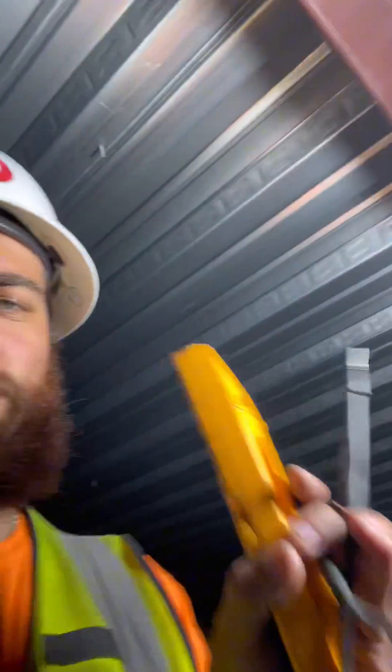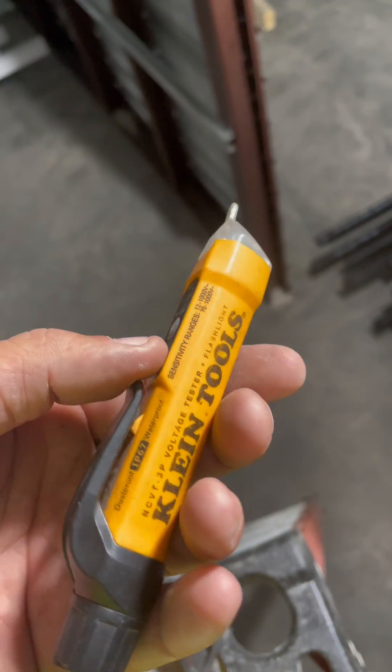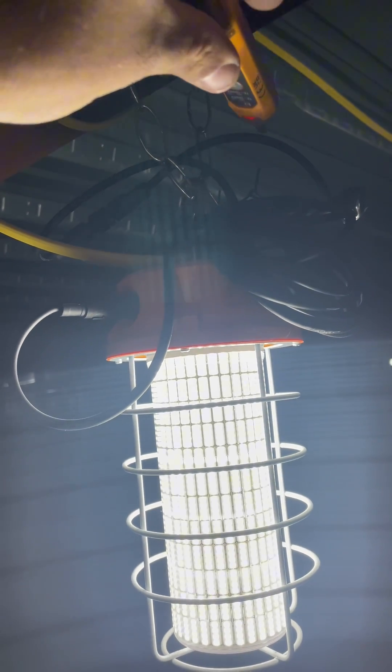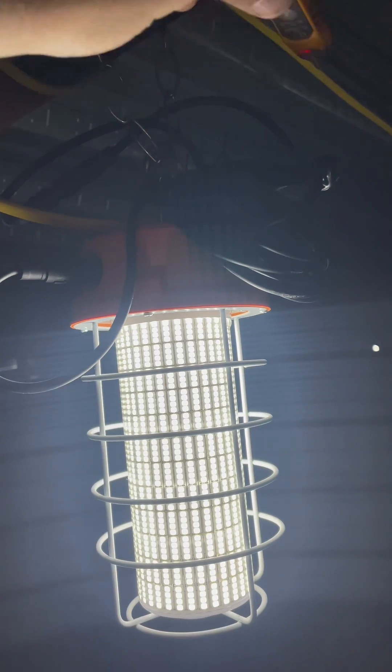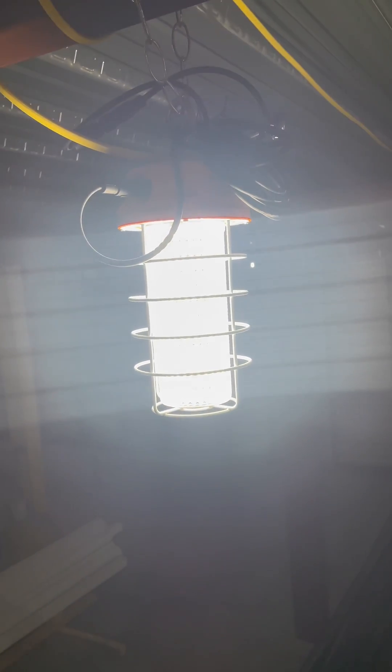What's up everyone, check this out. This is a prime example of why you need to carry these and stop carrying a tick tester. You would never expect to have any power coming from your ground, and in this situation I do. When I get close enough, within this whole vicinity, it's gonna tell you that there's power — it's detecting that power from inside these cables. You wouldn't think anything of it, but that's not the case here.